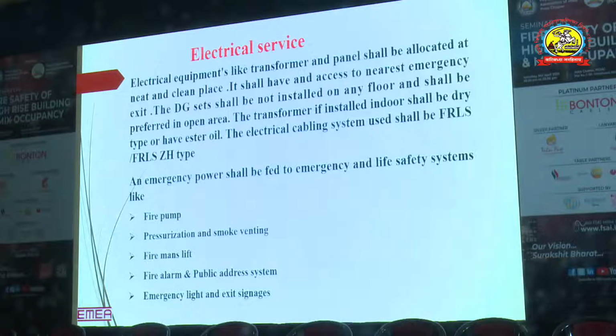Emergency power shall be another concept. Emergency power shall be fed to emergency and life safety systems like the fire pump, pressurization and smoke venting, fireman lift, fire alarm, public address system, emergency light and exit signage. For minimum emergency supply, providing a dedicated generator is a must for this equipment, 24 by 7.